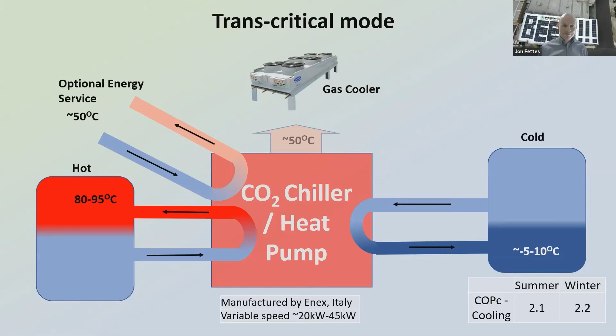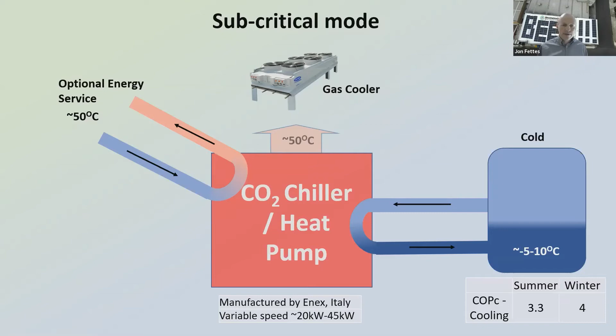So that's transcritical mode. This is subcritical mode. When we don't need to produce that super hot water, the compressor can switch to subcritical mode and act simply as a chiller. And the cooling COP is actually improved in that situation, but the overall system efficiency is reduced as the heat is wasted. But again, as a bit of a bonus, we can configure the system to intercept that heat and put it to good use for our space heating, or anything else for that matter. As you'll see, the COP is higher in the winter due to the efficacy and the extent of the gas cooling, sorry.